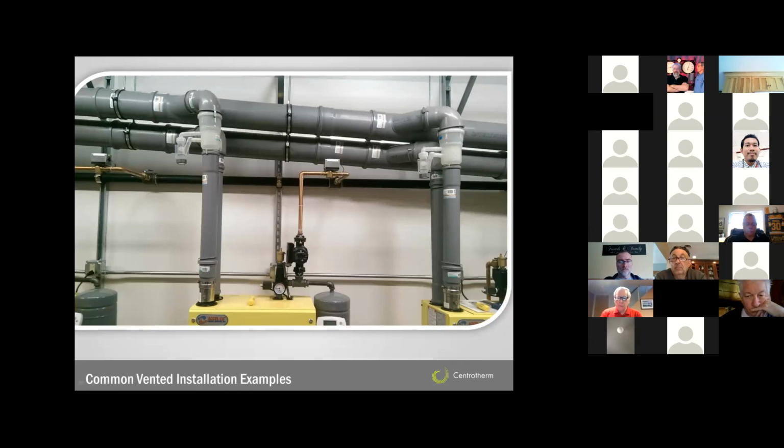They're handling the condensate through this trap here. They're just not showing the piping that would be going down to the condensate pump or condensate line. They just want to handle that condensate before you probably have dampers on the discharge of each boiler that close when the boiler's not firing. So they just catch the condensate here before it sits on that plate or that damper.